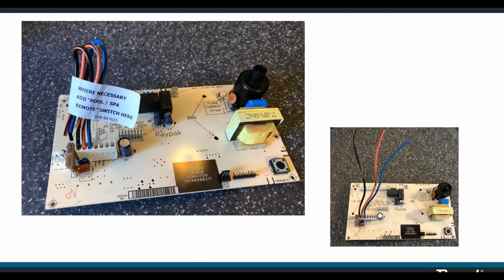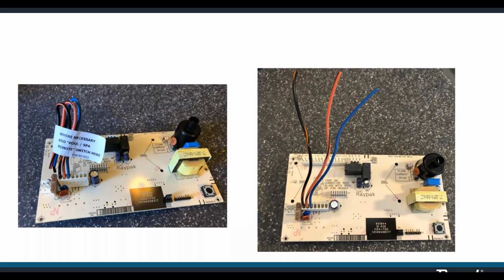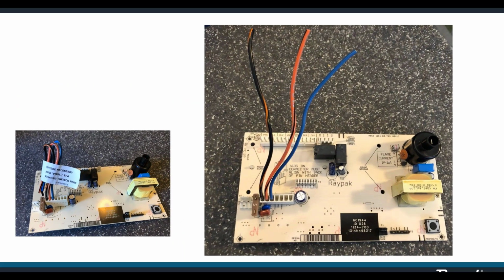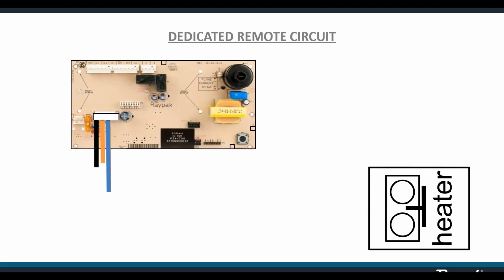On the board next to that 5-amp fuse, you'll find our dedicated remote circuit. It's a wire harness with 3 wires and a label for identification. The blue wire is the hot. That's going to be live with 24 volts when the board is powered up. The other 2 wires, an orange-black and a black-orange, will determine whether the heater turns on in pool or spa mode. So, blue's hot. You'll need a length of wire to span the distance from the heater to the automation system with at least 2 conductors. Blue wire, again, is hot, so we're going to extend and attach that wire to one side of the heater contactor on the remote.